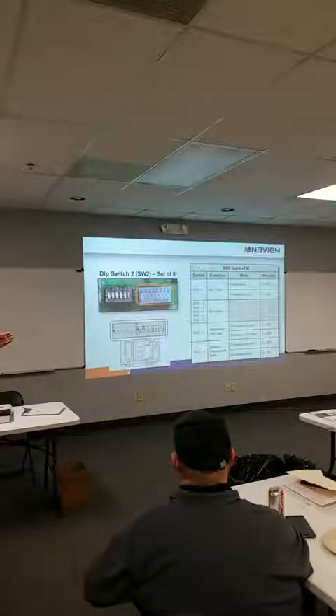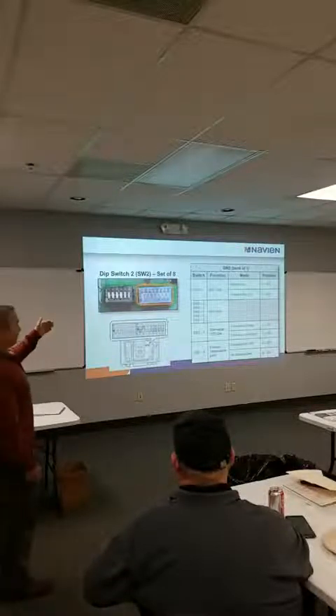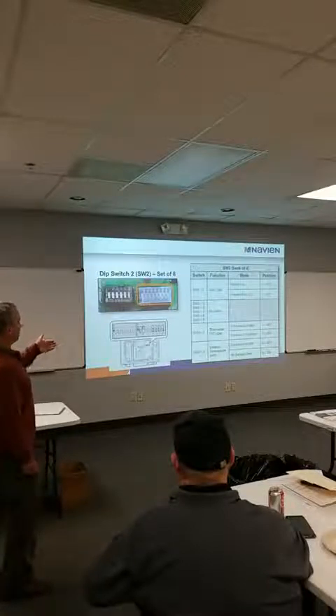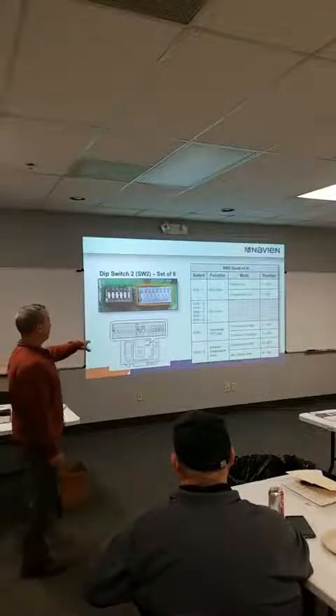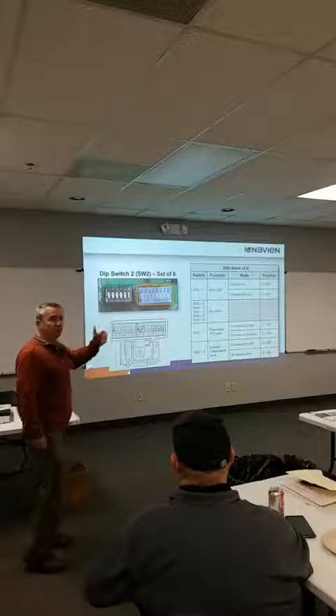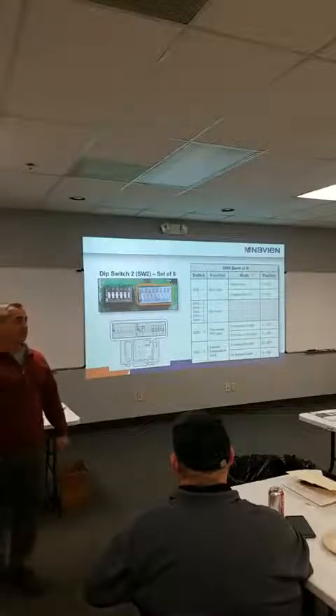And then your other dip switch is basically identical to the NHB. You have LP, if you're using a thermostat or not, and your exhaust limiter, your number 8 dip switch again if you're going to be over 150 degree return water temperature.